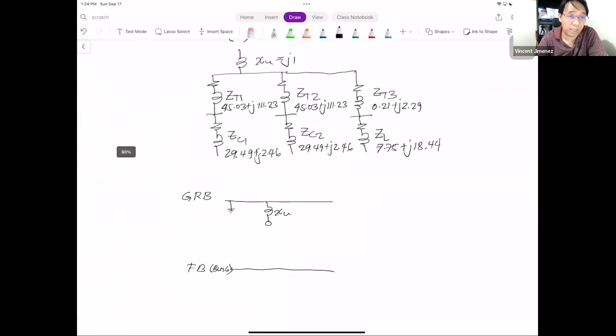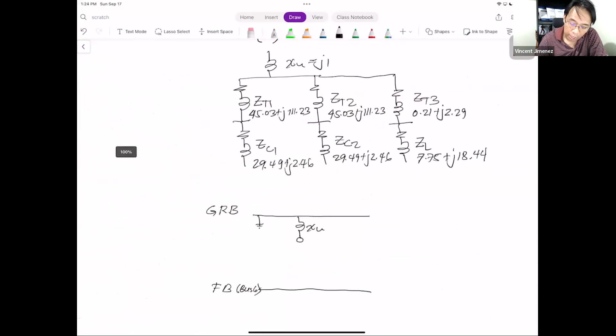Then look at the secondary side. Your secondary side is connected solidly grounded. Therefore you connect it to the reference bus ground. So you connect XT ZT3. Then you go to bus 6. So this serves as your zero sequence to bus 6.